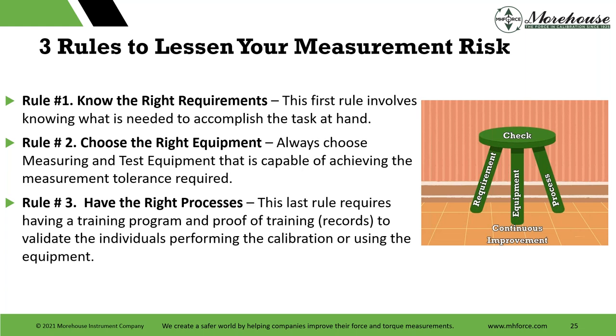Back to the rules — there are three rules. Rule one: know the right requirements. The first rule involves knowing what is needed to accomplish the task at hand. Rule number two: choose the right equipment — always choose measuring and test equipment capable of achieving the measurement tolerance required. Rule three: have the right processes. The last rule requires having a training program, proof of training, and records to validate the individuals performing the calibration or using the equipment.